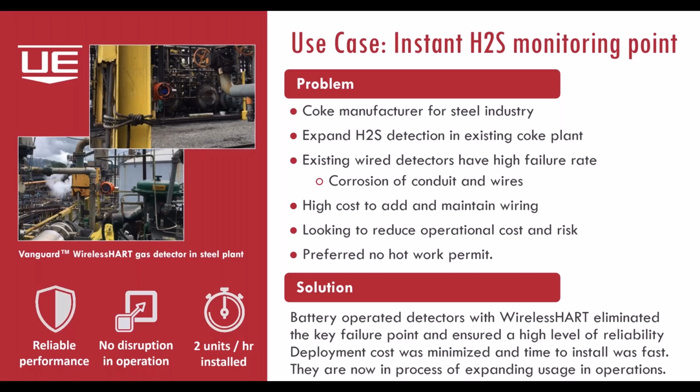But what they were having was a reliability issue specifically associated with conduit and wiring, not necessarily with the detector or sensor itself. So they were spending a lot of time doing maintenance on the wired detectors to make sure that they continue to be operating and reporting.